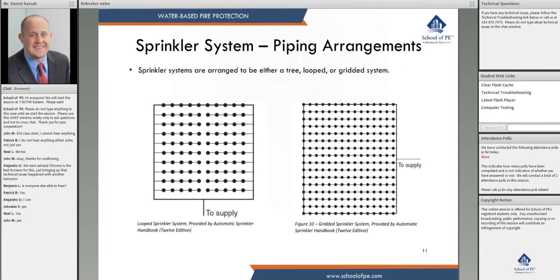Hydraulically, the gridded system is the best in terms of hydraulics, but it's also the most expensive. Usually we see a tree system — it's most economical and simplest. A loop system is somewhere in between: it has more hydraulic advantage than a tree system and doesn't cost quite as much as a grid system, but it still has more advantage than a tree.